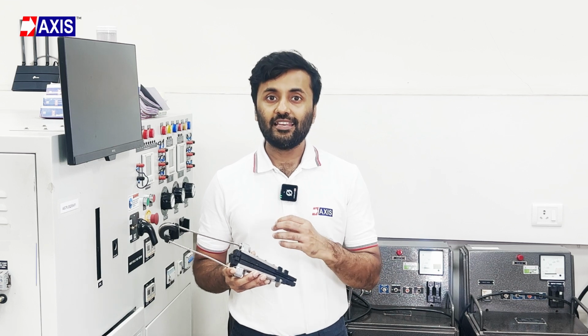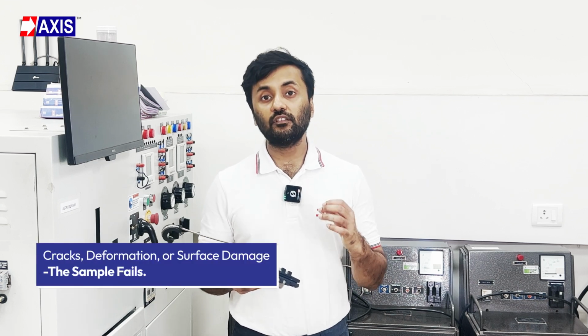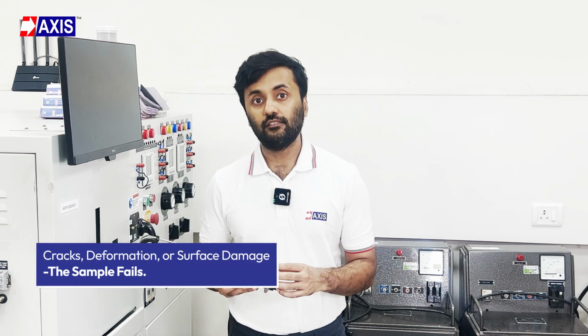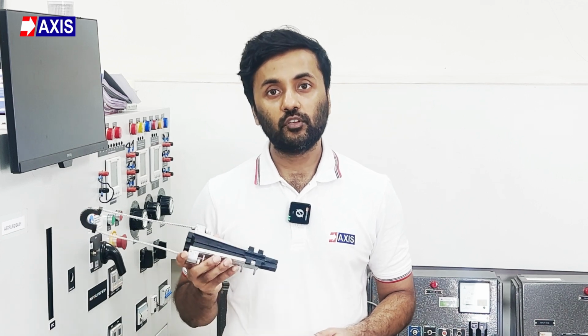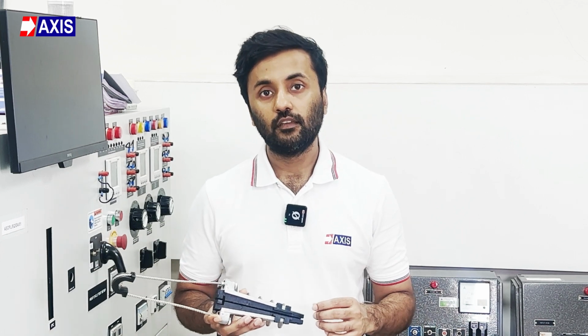After the aging period, test the clamp for dielectric performance and mechanical strength. What causes a failure? If there are any cracks, deformations, or surface damage, the sample fails. If the clamp fails the dielectric voltage test, or if it does not meet the tensile strength requirement, the sample also fails.